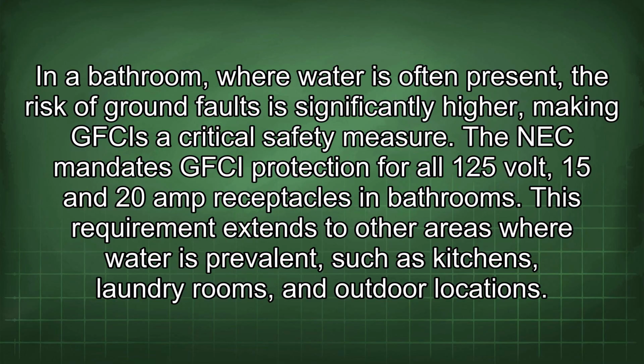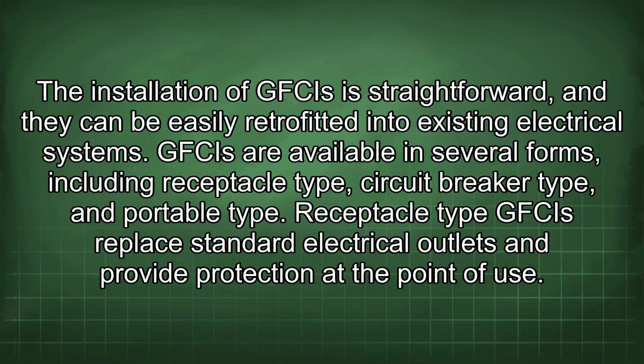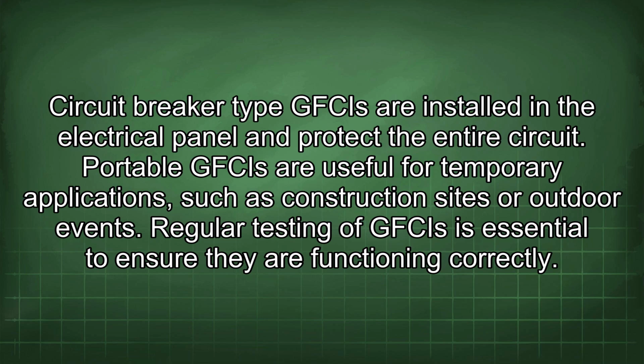The NEC mandates GFCI protection for all 125-volt, 15 and 20 amp receptacles in bathrooms. This requirement extends to other areas where water is prevalent, such as kitchens, laundry rooms, and outdoor locations. The installation of GFCIs is straightforward, and they can be easily retrofitted into existing electrical systems. GFCIs are available in several forms, including receptacle type, circuit breaker type, and portable type. Receptacle type GFCIs replace standard electrical outlets and provide protection at the point of use. Circuit breaker type GFCIs are installed in the electrical panel and protect the entire circuit. Portable GFCIs are useful for temporary applications, such as construction sites or outdoor events.